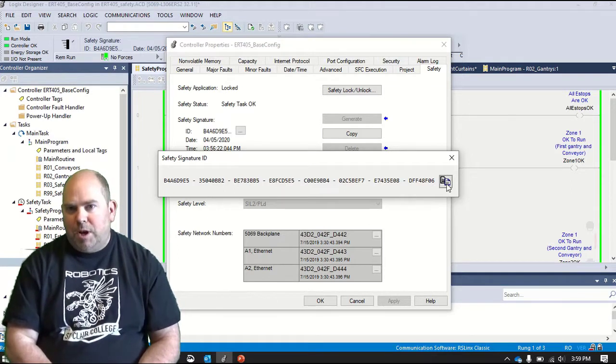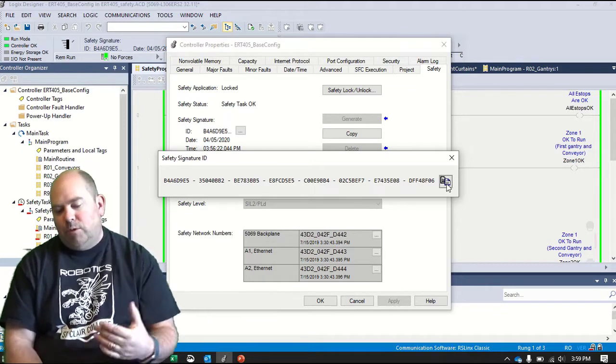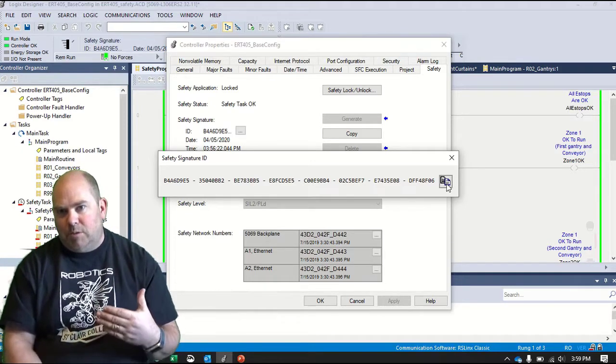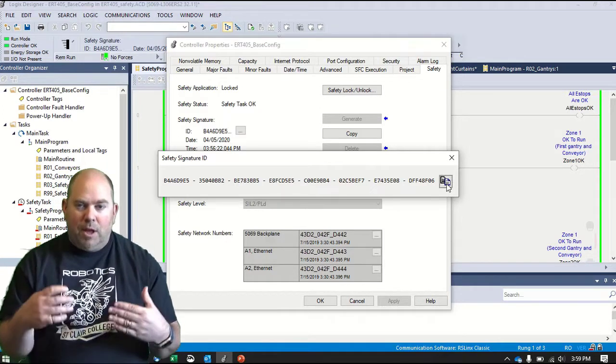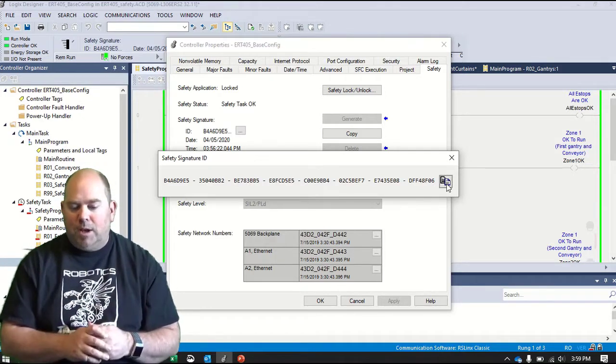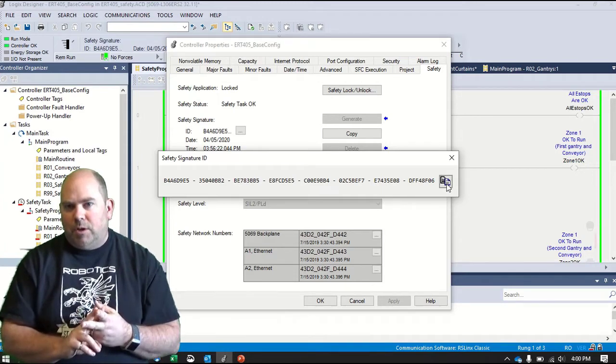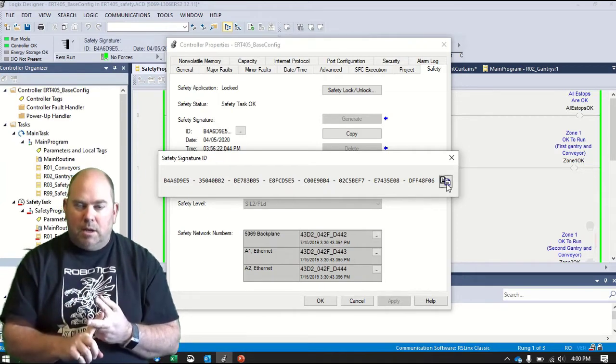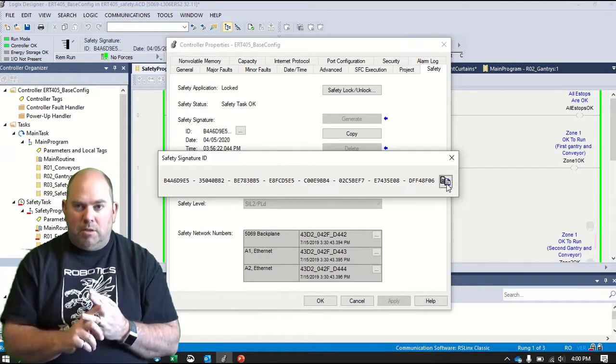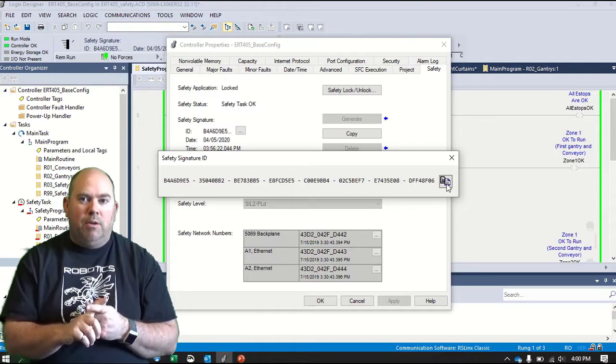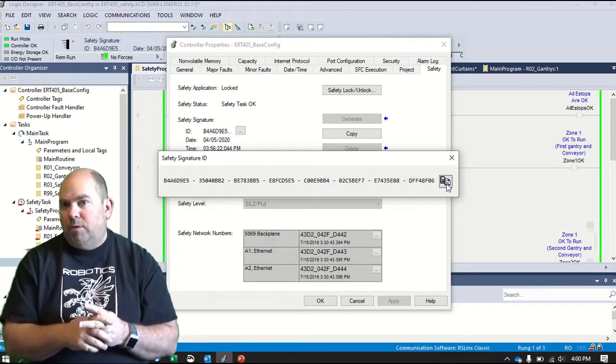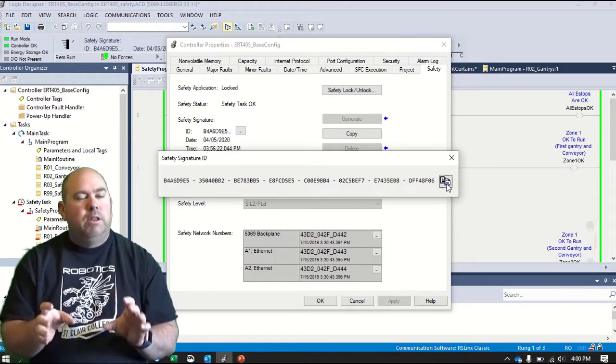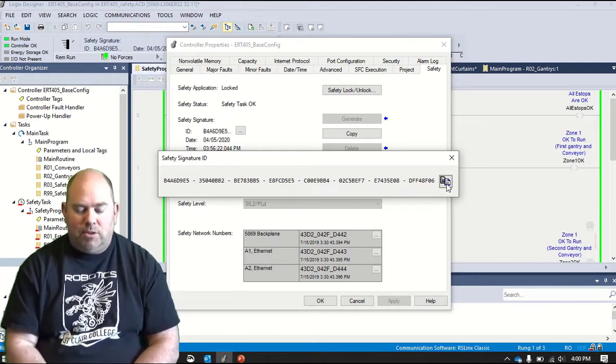Okay, so if anyone were to try to make changes to this, you can always check what is the current signature that's in the PLC versus what was it when I left, and you can tell if somebody has messed with that. And this is basically your legal defense of what was the software when I left it. Okay, so remember how we talked about all the different things that a safety system has to do? It has to be able to be locked out and protected. You need to be able to validate that the logic is good. You need to be able to check that people can't mess with the wiring. It should shut down. If that happens, all devices need to be dual channel, and all devices should be redundant for the output. So everything we've done here covers all those bases. So this is a valid safety system.